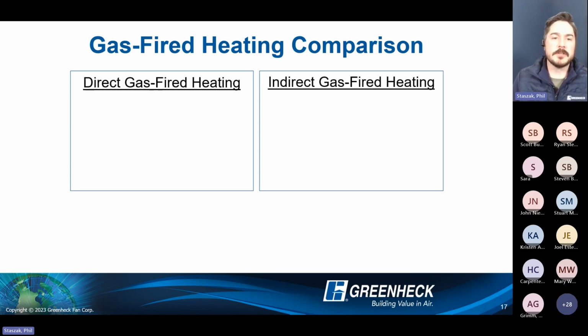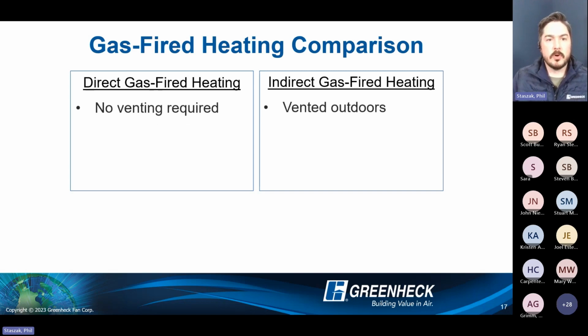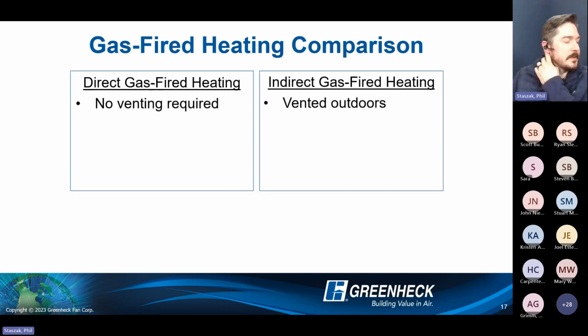So, interesting conversations. If you're looking at a gas heating option, direct gas fired is definitely going to be the one that makes the most sense from an upfront cost, long-term cost, and overall operating standpoint, if you have access to gas and your gas costs are less than what electricity would be. The advantage with direct gas fired heating is there's no venting required. We still get this question from time to time: if a unit is installed inside, where does the venting go? It's literally a direct gas fired burner, so it's an open flame in the airstream.